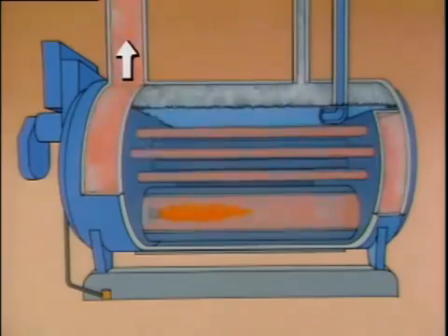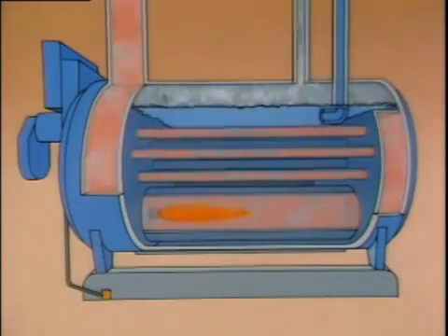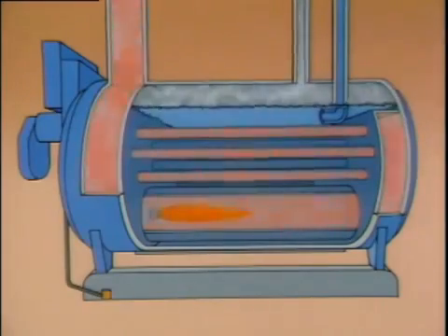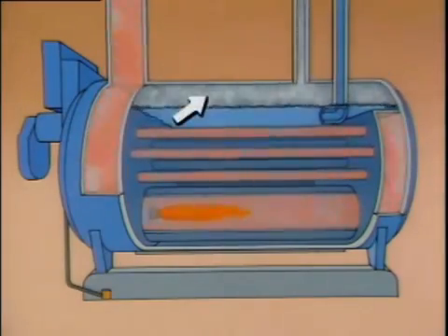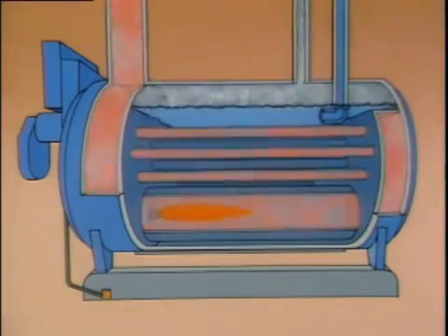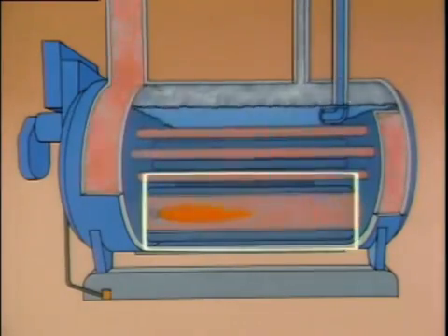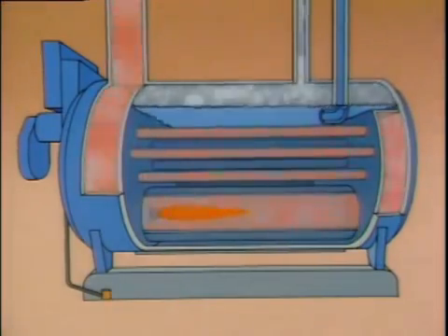The combustion gases flow out of the boiler. As the water in the boiler is heated, some of it turns to steam. The steam-water mixture is lighter than the cooler water in the boiler, so it tends to rise. Steam collects above the water level, then flows through the outlet and into the plant. The feed water, which is cooler and heavier than the steam-water mixture, flows to the bottom of the boiler. It's heated in the combustion area, and the cycle continues.